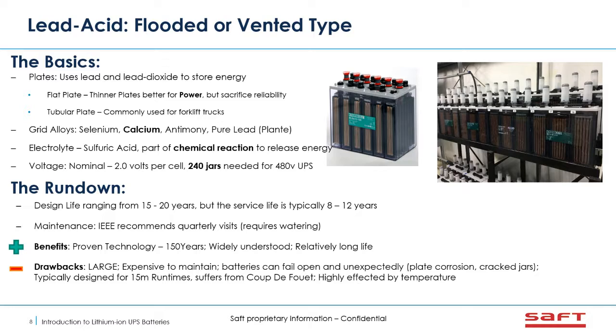The main benefit of this technology is that it's a proven technology, roughly 150 years of existence. It's widely understood, relatively long life compared to some of the other technologies that are out there. I would say the drawbacks are that these are large batteries, relatively expensive to maintain. They can fail open and unexpectedly. They have cracked jars, plate corrosion, and they're typically designed for the 15-minute runtime. We see a trend in the market to reduce runtimes, so these typically have a little bit longer runtime associated to them, and they are pretty highly affected by high temperature applications as well, where aging occurs faster.